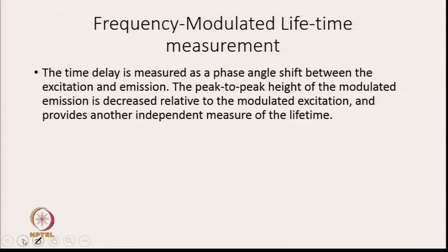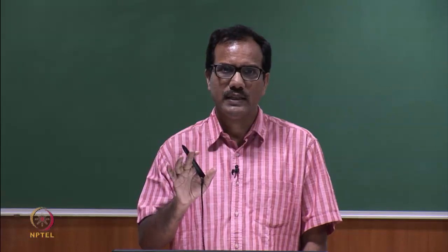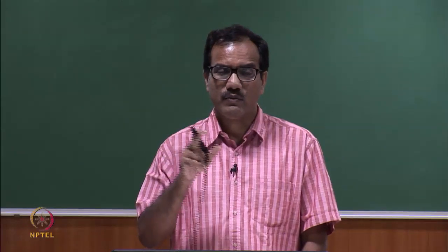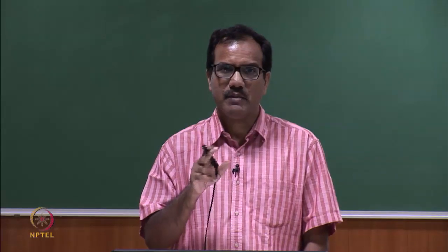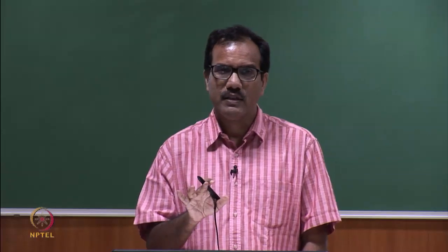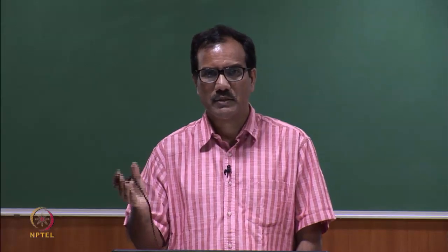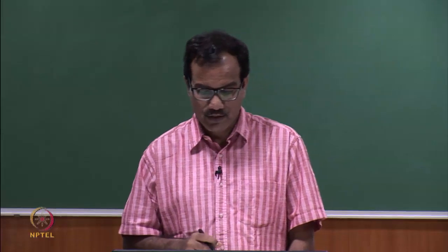So, what we are looking at here is that the time delay is measured as a phase angle shift between excitation and emission. What we did, first we excited the fluorophore with light which is intensity modulated, and now we are looking at the fluorescence emitted, which has the same frequency, only it is phase shifted from the excitation source spectrum and is modulated, and now we are measuring the difference in phase.